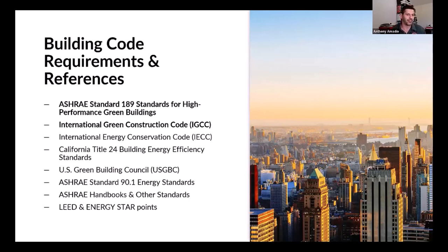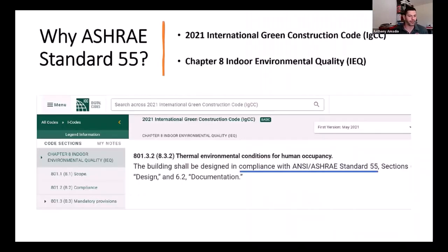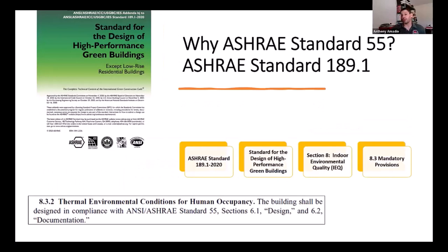But when you get a chance to show them, hey, look, ASHRAE Standard 55, when you're talking about high performance buildings and green construction, LEED buildings, this is required. That's fine if you don't understand it. I'm happy to explain it to you the best I can, but it's required and we're going to do it. It's also referenced in many of the ICC codes and the US green building codes. There's a note that the building shall be designed in compliance with ANSI/ASHRAE Standard 55. This is in both the IgCC, the International Green Construction Code, and also in Standard 189.1.